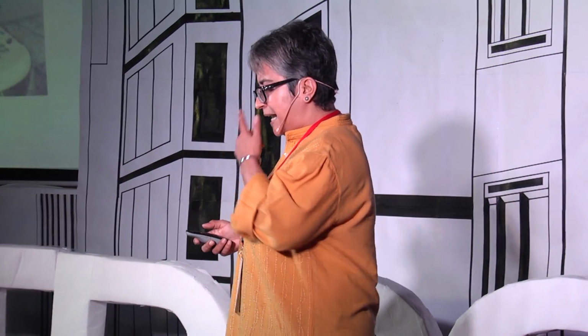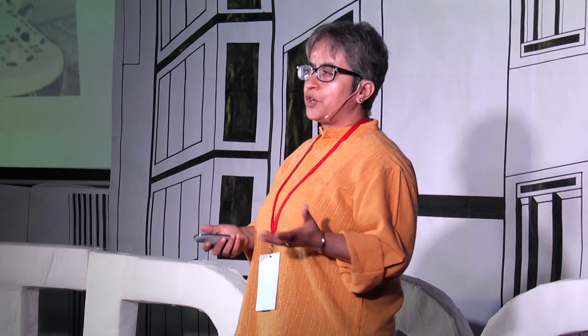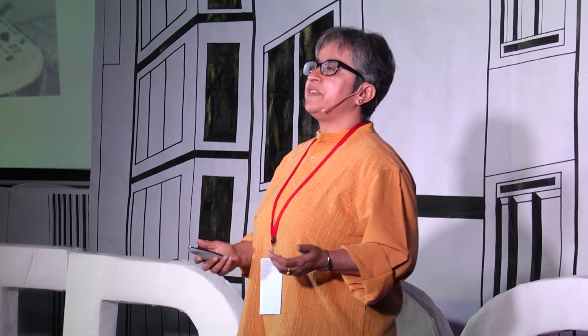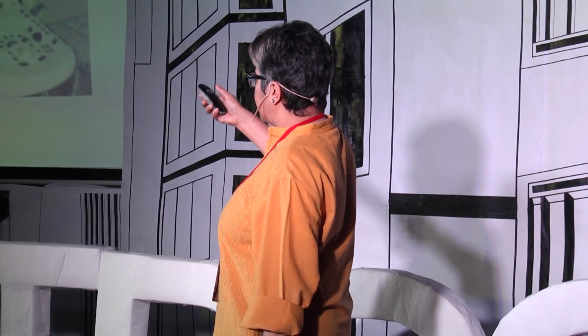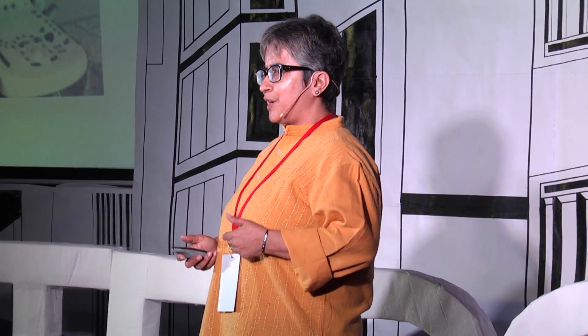Now, long, long back, about 50, 60 years back, the piezoelectric membranes were concave shaped, and that's what radiated ultrasound. And when the sound waves came back as reflected echoes, they once again converged at the focus, and that's how images would be made. In the last few decades, things have changed because of digital signal processing and application-specific integrated circuits. So now focusing can be done by applying time delays to waves that emanate from these tiny crystals that dot the surface of the probe. So that's how modern ultrasound machines image through convergence.